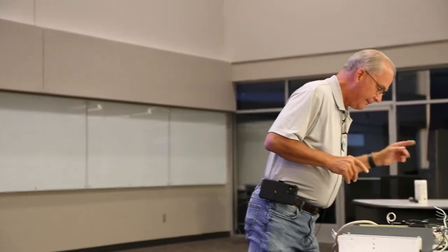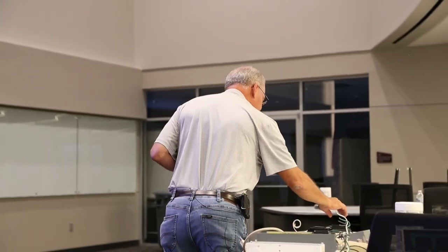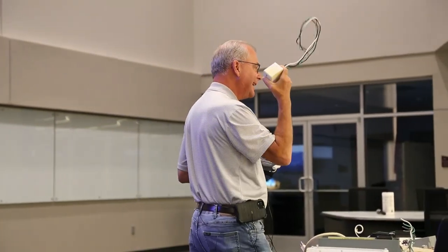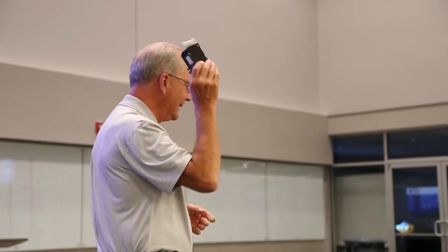One little tidbit: for those of you with Square D branded breakers, if your panel is full and you're trying to get a surge protection unit in, UL rates Square D breakers and allows two connections on 10 to 30 amp double-pole breakers. The breaker has two little bends in the plate that clamp the wire down, allowing you to tap it. So if you have a dryer on a 220, this would allow you to do a tap on the 220 side and add surge protection — two connection points. That's a little tidbit of knowledge from the Square D side.